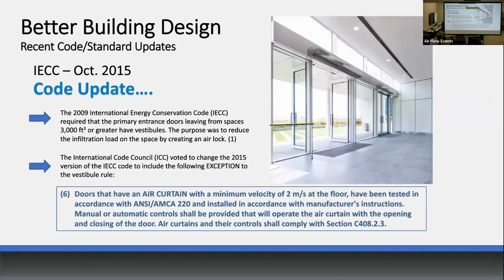So we knew this. There's 3 major air curtain manufacturers in the United States. We took this and had a study done, which we first took to IECC. In 2015, there was a code update stating you could use an AMCA certified air curtain in place of a vestibule. It must be AMCA certified, and here's some of the criteria. Well, number 6 was the update for 2015. It must meet a minimum velocity of 2 meters per second at the floor. It must be AMCA certified, and it must operate off of a door switch.